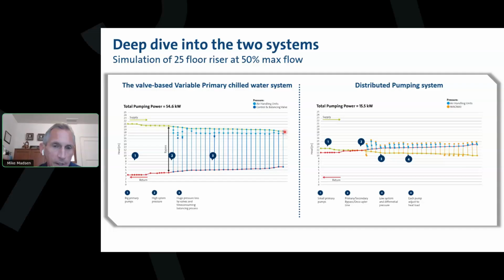These 2 close together dots are the pressure drop through my coil and my air handler. And from here to here are all those control valve losses we talked about. So we've got a lot of control valve losses when we're operating at 50% of max flow. That's what we'll eliminate with distributed pumping. So variable primary, where we're using about 55 kilowatts.